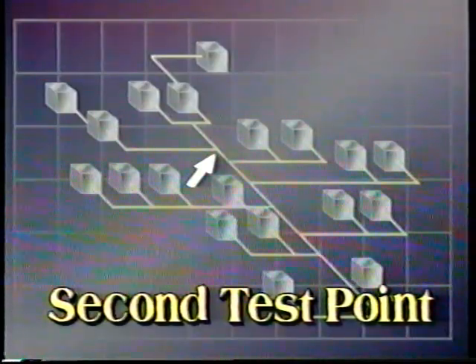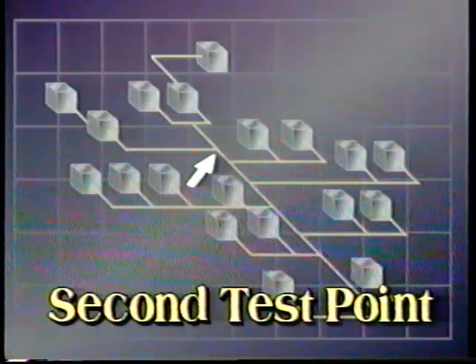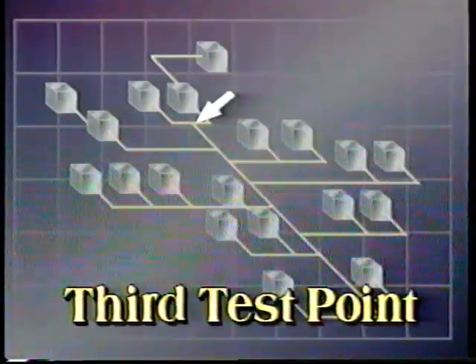If the test reveals contamination, then this portion of the operation is functioning correctly. The problem must be occurring in that part of the operation. Then use the half-split method again and choose a midpoint in that part of the operation for your next test. Using the half-split technique allows you to find the cause of a problem quickly with a minimum number of tests.